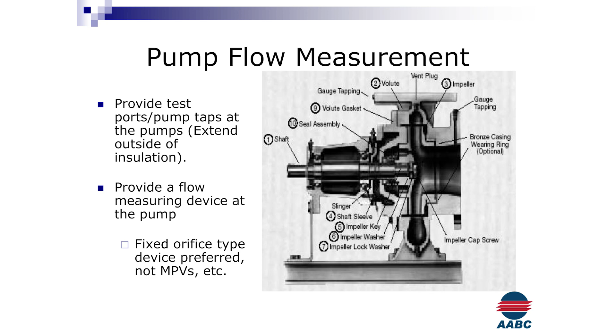This is just a good detail. It shows what we would need or what would be expected for us to find in the field. The detail is the most important thing, because if we get out there and the detail didn't show gauges or the ability to have a piece plugged in or installed, we have no way of enforcing that the installer didn't put it in per the detail. So having a very detailed detail, we're able to hold the installation contractors a lot more responsible.